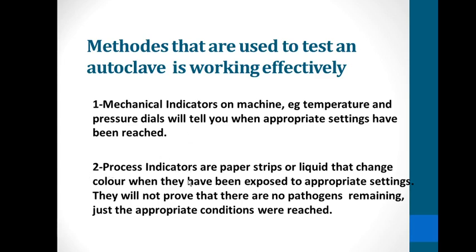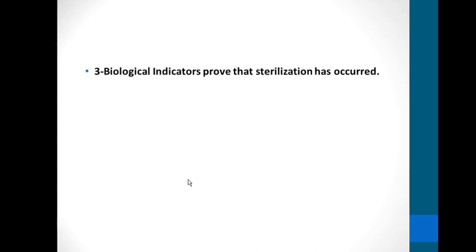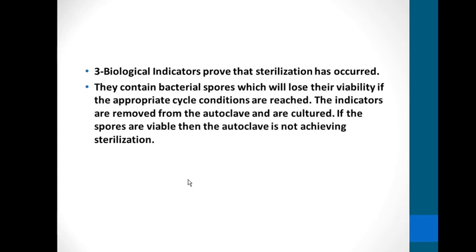The third type, and most important, is the biological indicator, which actually proves that sterilization has occurred. This is a very important method for testing whether the autoclave is functioning well. They contain bacterial spores which will lose their viability if the appropriate cycle conditions are reached. The indicators are removed from the autoclave and cultured; if the spores are still viable, then the autoclave is not achieving sterilization.